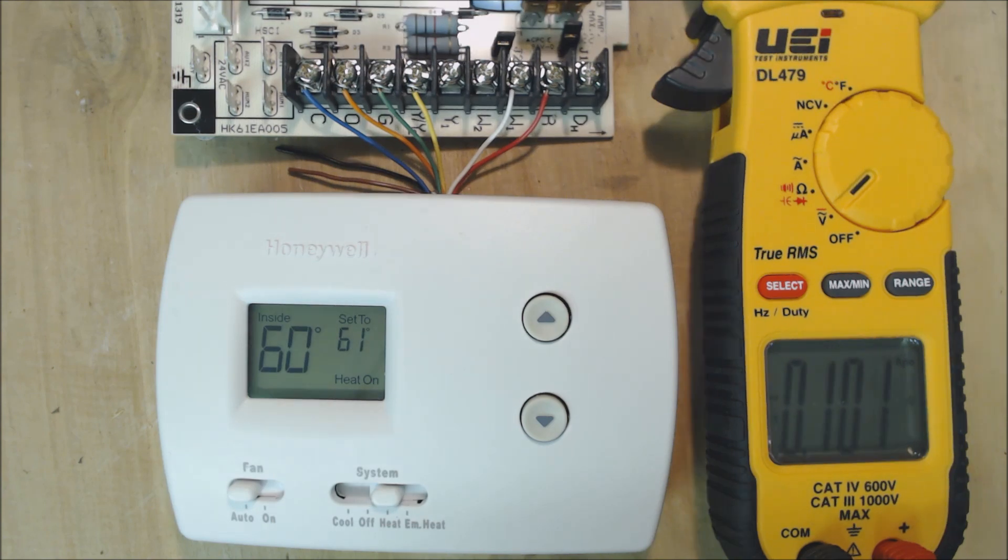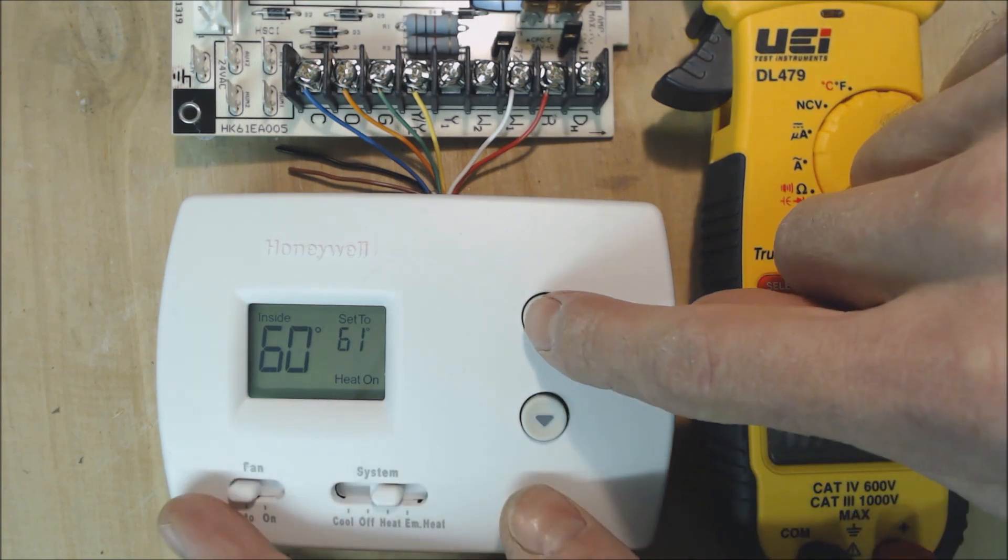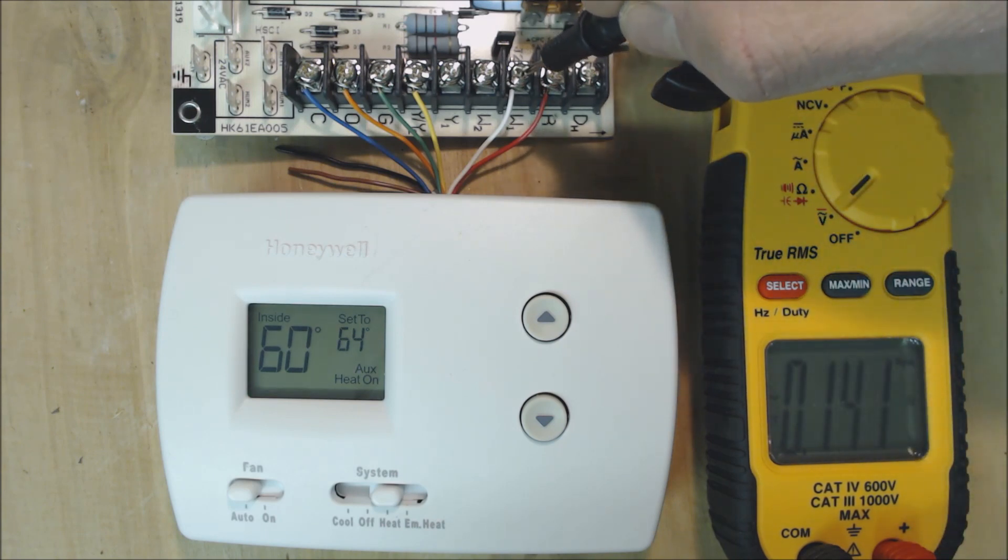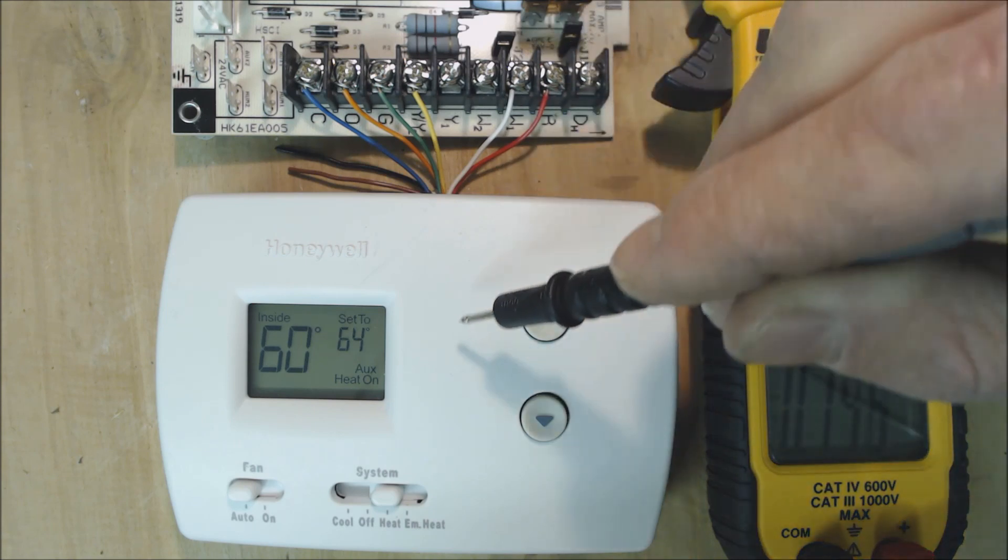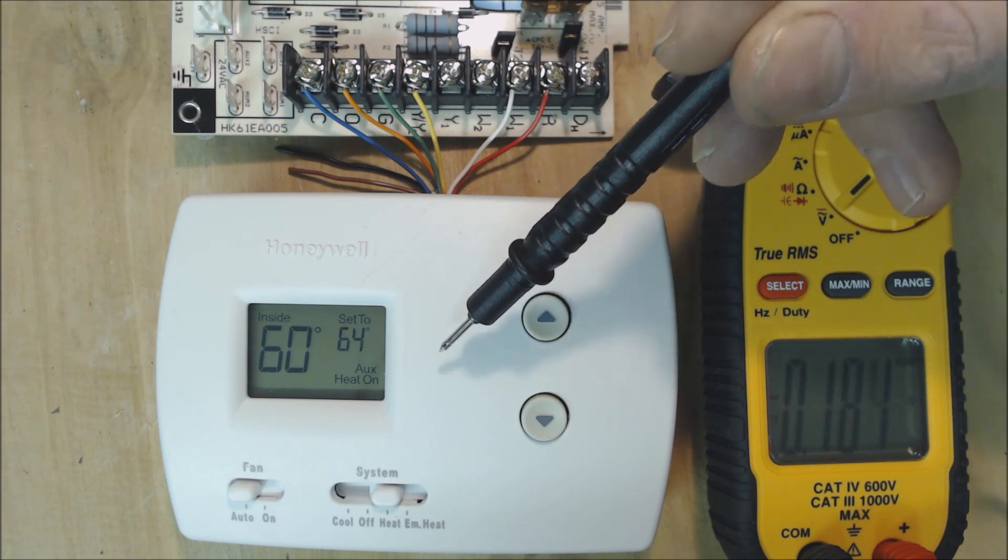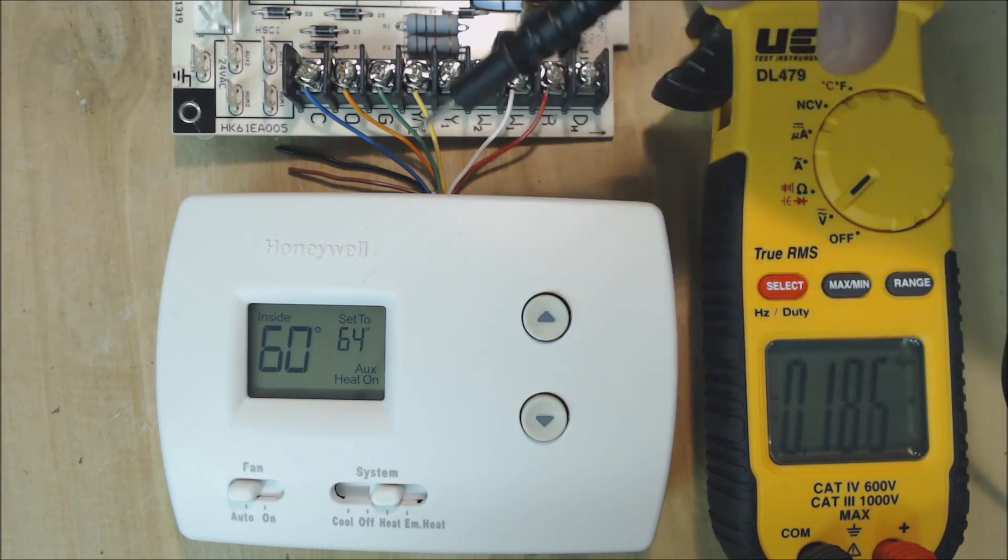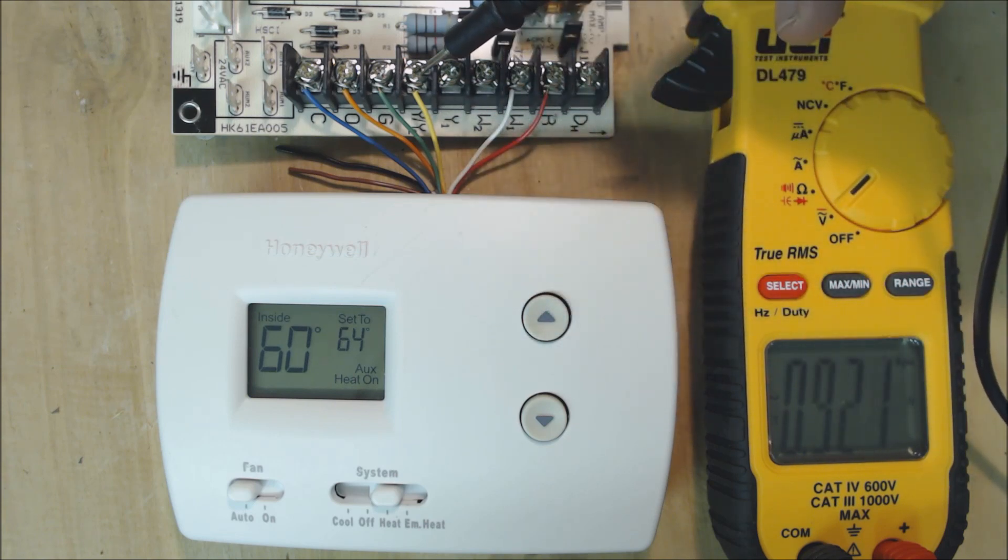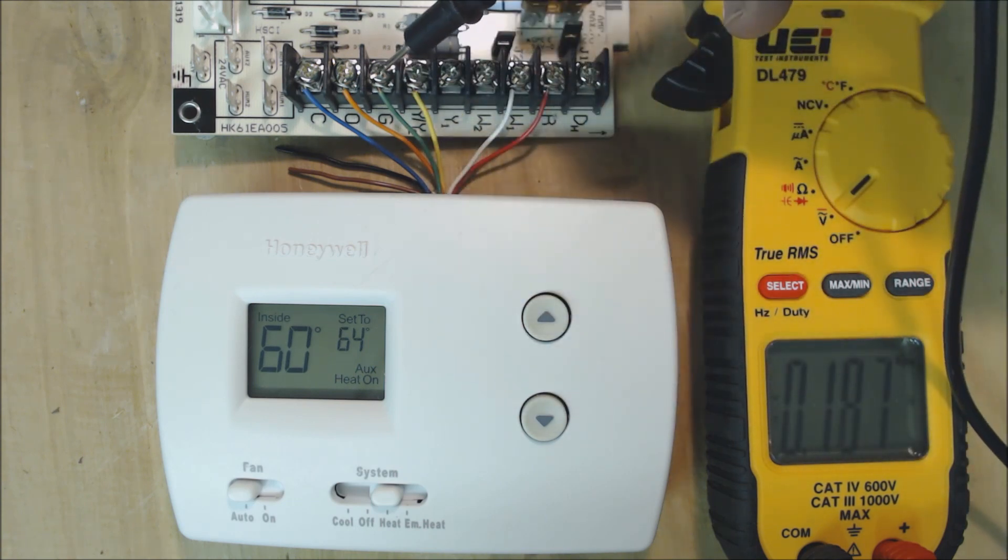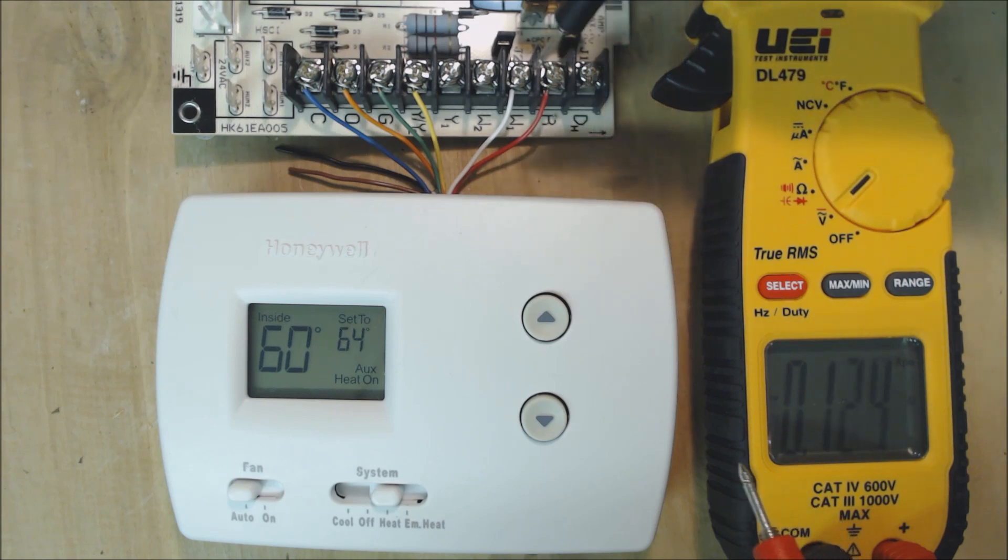Now if we want to test auxiliary heat, we're going to turn this several degrees up higher, and then we should have our auxiliary heat turn on. When our auxiliary heat turns on, we're going to be able to test from W to common. We're going to get 24 volts because R comes into the thermostat and now touches W. It touches Y still because the heat pump is running, but you also have auxiliary heat running, and R touches G.